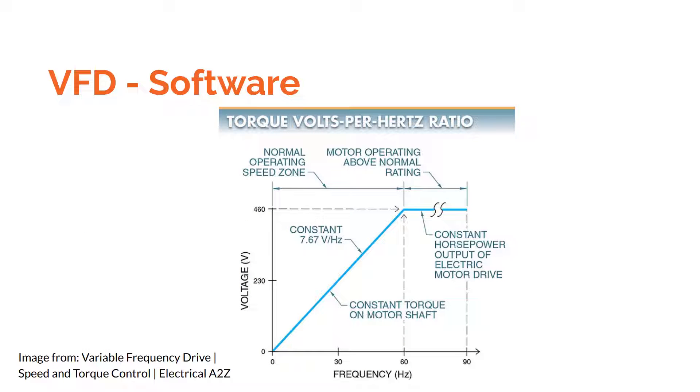The control method of this VFD is V over F, which maintains a constant relation between the outputted average voltage and the frequency up to the rated speed. After going over all of this, the VFD may seem a bit complicated. Are there any simpler options for induction motor speed control?